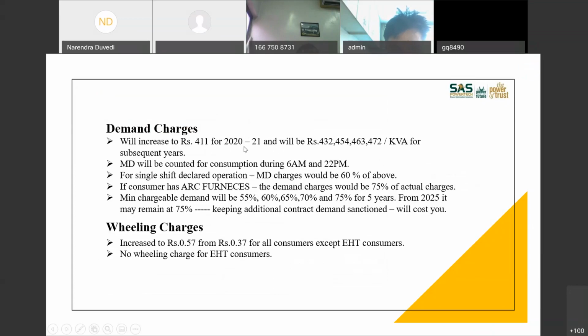That's what the order says. MD will be counted for consumptions during 6 a.m. to 22 p.m. So within this period, whatever you consume, standard 30 minutes window will be executed by MSEDCL trivector meters, and the maximum demand consumed between 6 a.m. to 22 p.m. averaged over 30 minutes will be taken as MD. This is a new thing which they have introduced now.